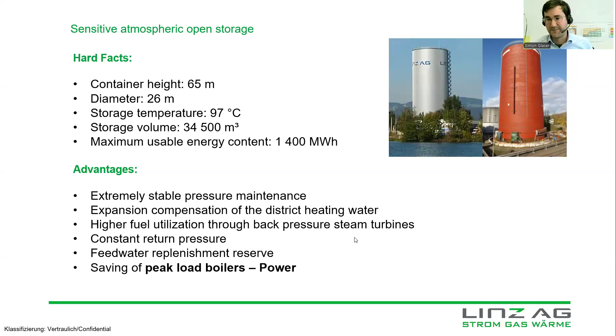We also have other advantages because of this storage. It's possible to have extremely stable pressure maintenance, expansion compensation of the district heating water, and higher fuel utilization through our back pressure steam turbines. Constant return pressure and feed water replenishment are other benefits. But most importantly, when it comes to heat peak loads, it saves the runtime of our heat peak load boilers, as Simon and Lars mentioned before. This is also a really big advantage.